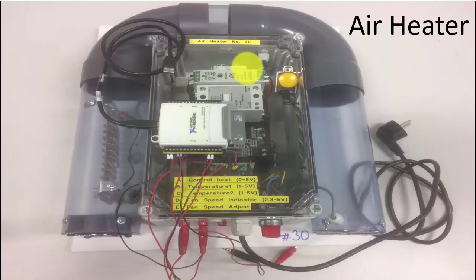If the controller is not working properly, you can try to adjust the PID parameters on the Fuji controller manually using the Skogestad method or another method, such as the Ziegler-Nichols method. Or you can also try the auto-tuning functionality that is part of the Fuji controller. When you are able to control the mathematical model using the Fuji controller and find some proper PID parameters, you are ready to test the Fuji controller on the real process.